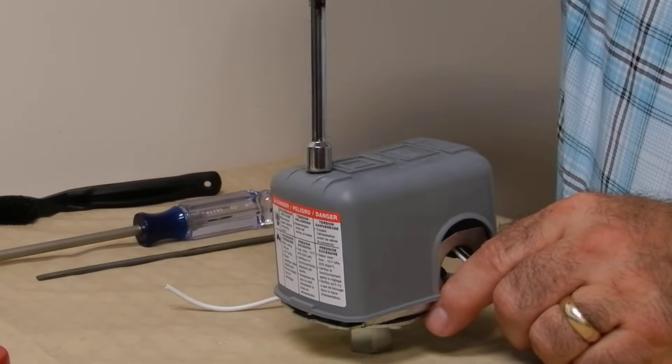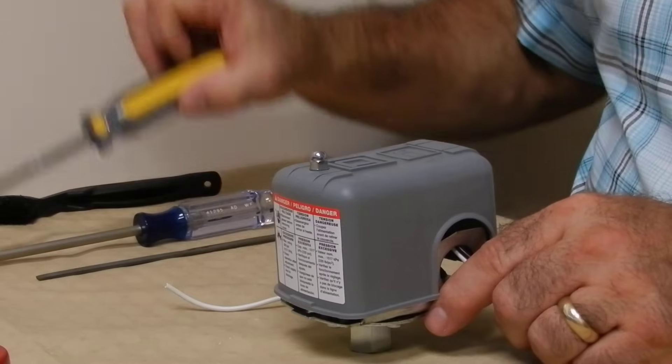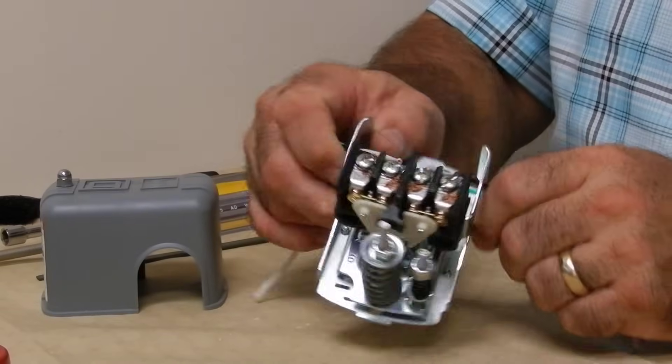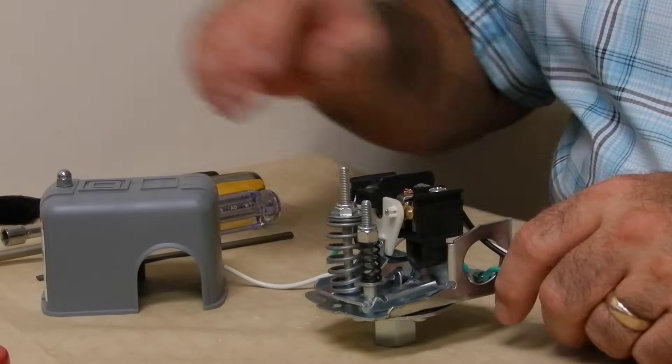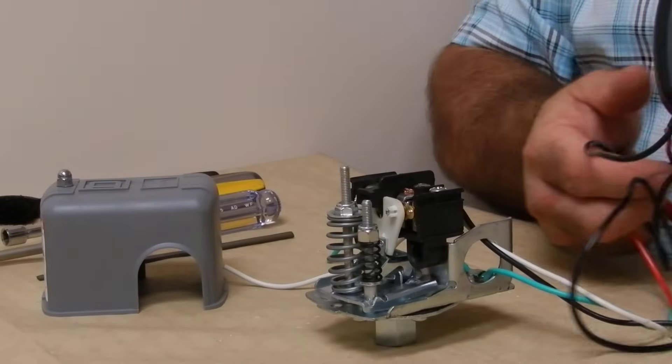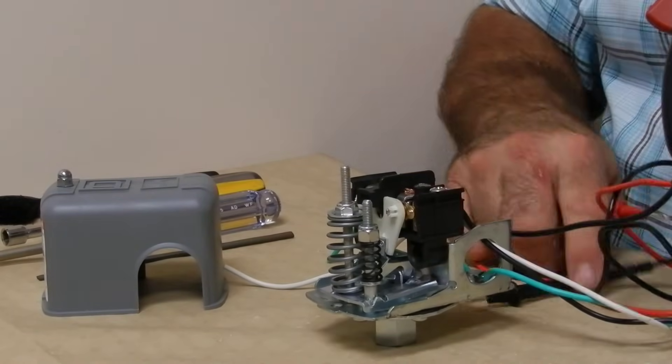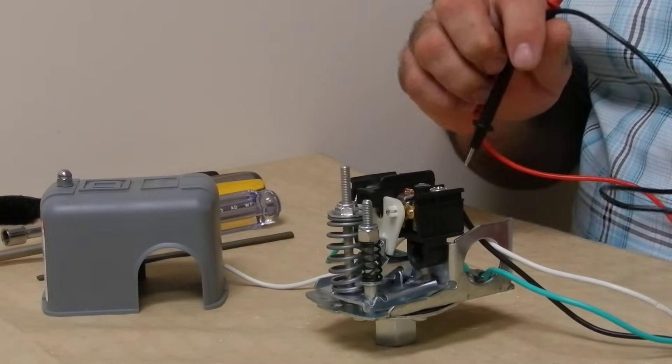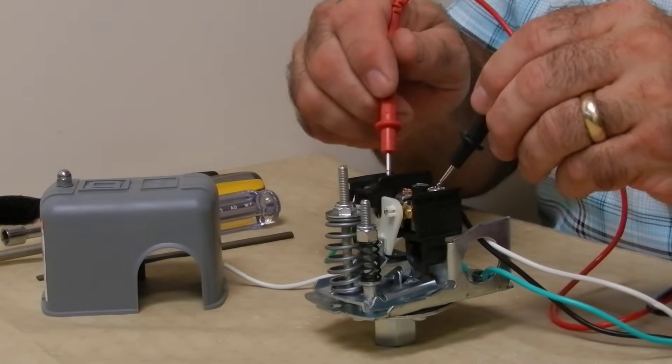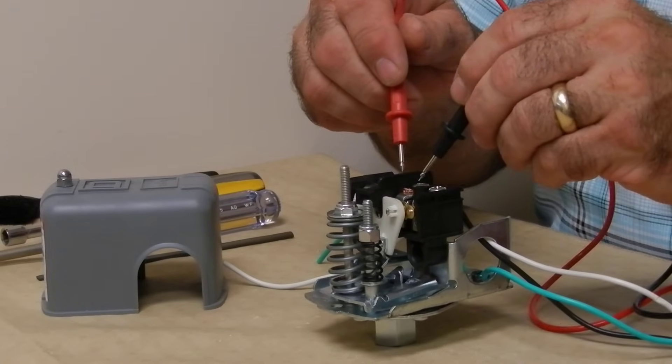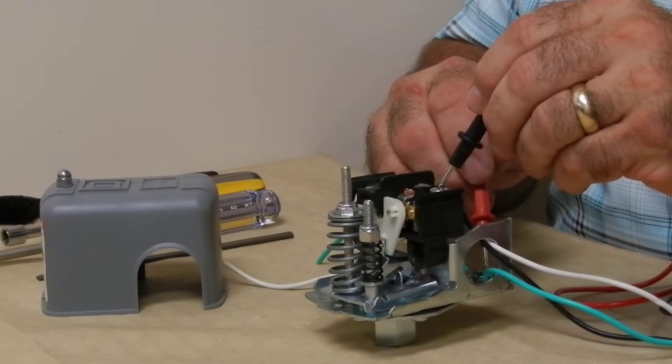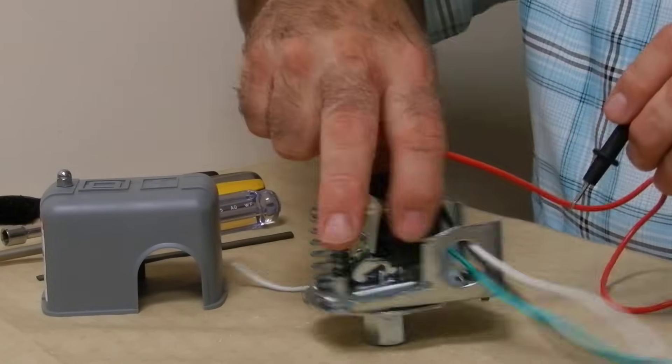Remove the lid. Inside you will see four electrical connections. Make sure the power is off by using a small electrical test meter to test for AC voltage. Check across the outside terminals, the inside terminals, and then each terminal to ground, like this.